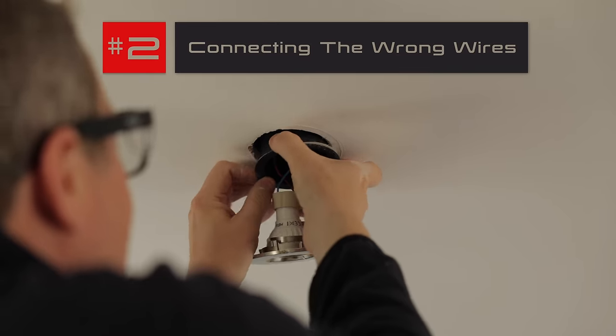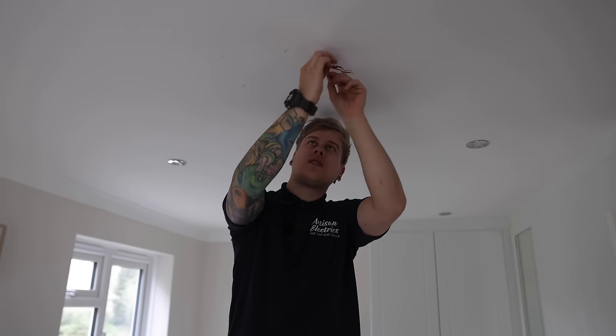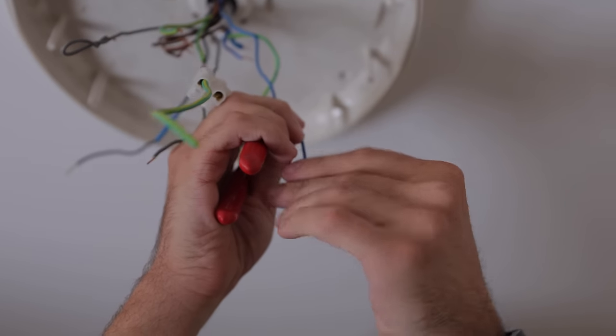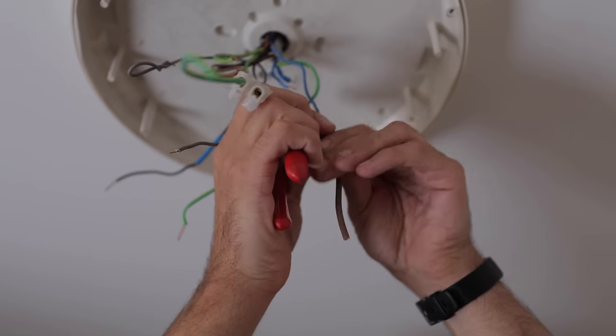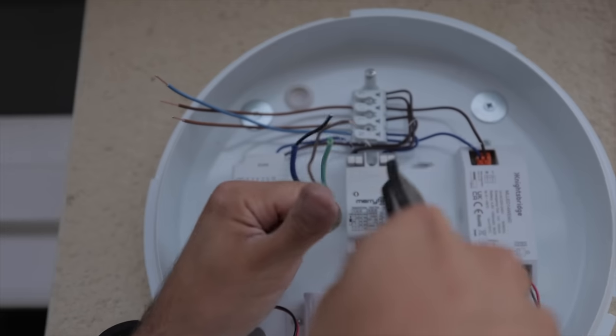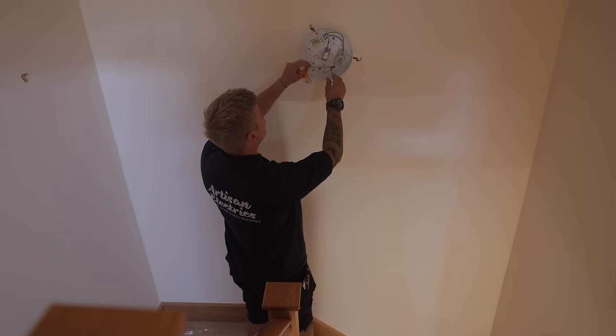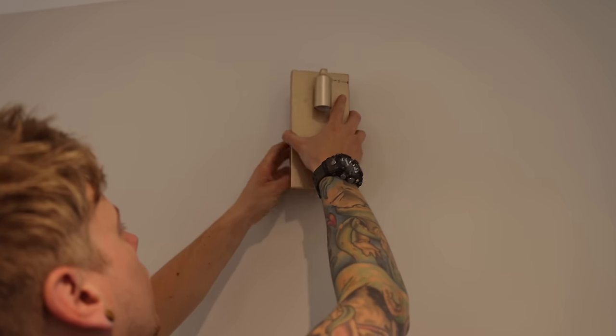Another classic faux pas when changing a light fitting is connecting all the reds and blacks together or the blues and browns together. People think that red and red goes together and black and black, but that's not always the case. Sometimes a black wire is actually sleeved as red and it could be a live conductor and you put it in together with a live, you're going to have a big bang or vice versa.